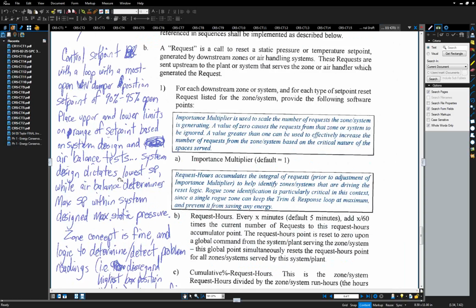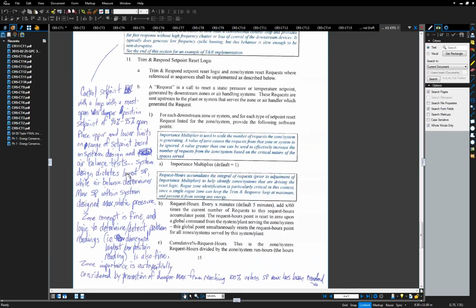Yeah, I was reading through this, and I was reading through the Trim and Respond where you adjust and check every so often and go up or down. We kind of are doing the same thing when we use a loop to keep the most open VAV damper at 90-95%, depending on the area. And that's worked really well, but I was reading through some of the other comments and the things that it's being used for, and certainly there's reason to think that there may be some advantages to what I saw written in the new control sequence.